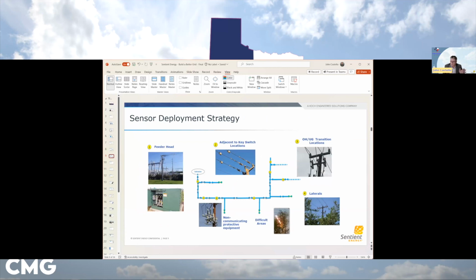We talk about placing sensors just outside of substations, at the feeder head, to give visibility downstream, especially for substations without SCADA. We call this SCADA Light, or poor man's SCADA, giving information about what's going on at the substation and out on the feeder.